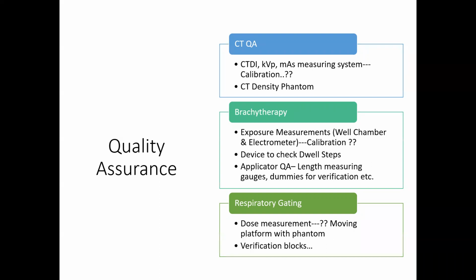Most of the brachytherapy equipment comes in contract with the machine itself, but certainly we need to verify that this is a part of the contract. That is something like a well chamber and electrometer. Again, at the moment, there is no calibration laboratory available in Pakistan, so we need to send those well chambers and electrometers abroad for calibration. And certainly a few other checks, like dwell step checks and QA for the applicators. One type of QA is the fluoroscopic QA, and the second type is the physical QA, which is the length measuring device, length measurements and dummy verification. So we get length measuring devices and dummies for the verification for QA.